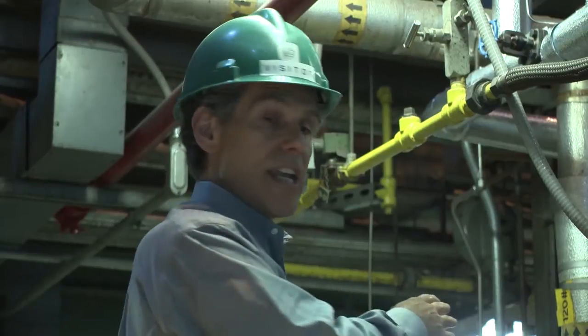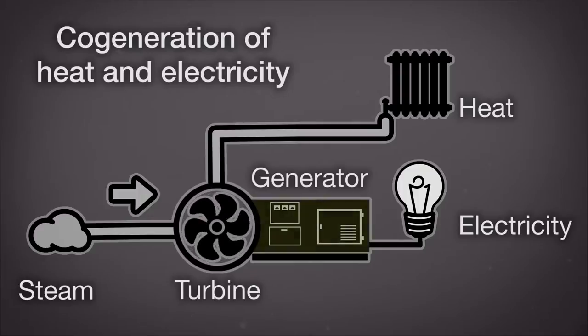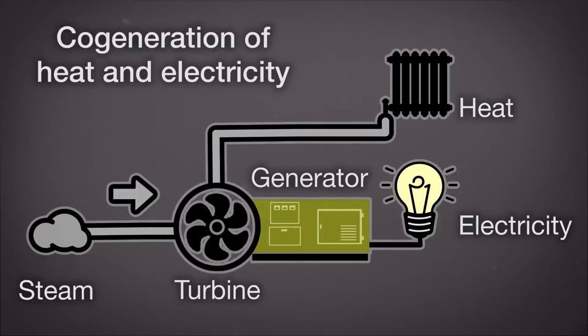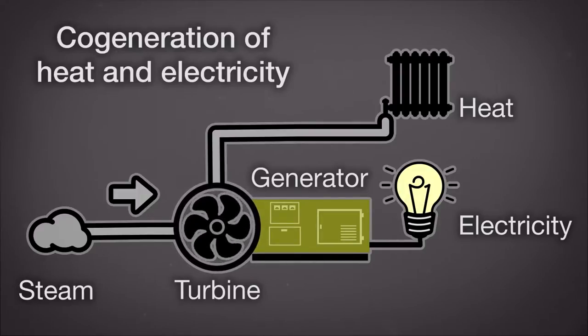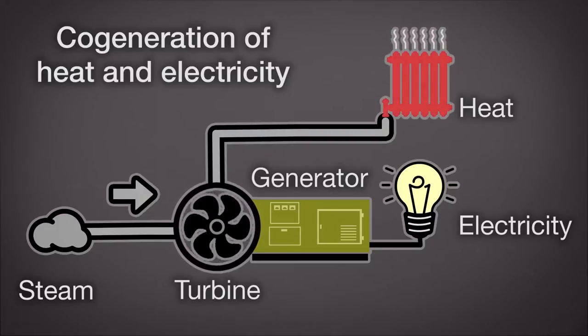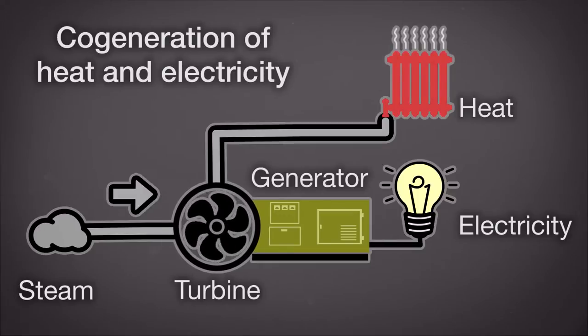The steam is then piped into the next room where it turns a turbine, which turns a generator, which generates electricity. In our case, that electricity is used to power about 40 percent of the Dartmouth campus electrical needs. After passing through the turbine, the steam goes out to campus where it heats buildings and heats water.